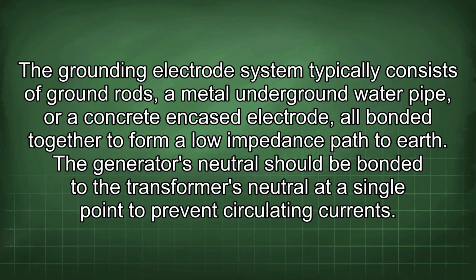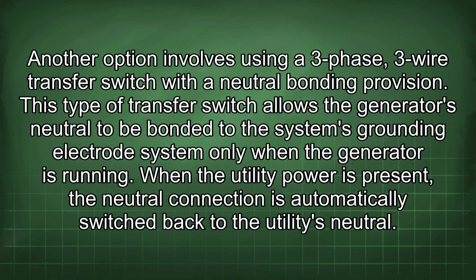The grounding electrode system typically consists of ground rods, a metal underground water pipe, or a concrete encased electrode, all bonded together to form a low-impedance path to earth. The generator's neutral should be bonded to the transformer's neutral at a single point to prevent circulating currents. Another option involves using a three-phase, three-wire transfer switch with a neutral bonding provision.